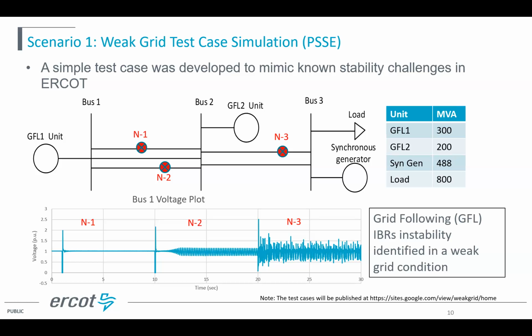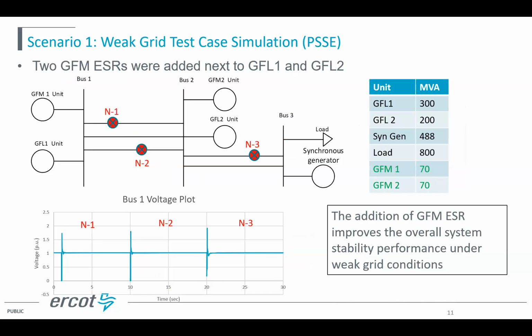And by the way, we posted this test case to the Google website, so you can download it. And then we add 2 grid forming batteries, each 70 MVA, to bus 1 and bus 2, and then we repeat the same simulation. And you can see it is stable even at N-3. So basically, it proved the concept that grid forming really helps improve the overall stability performance in weak grid conditions.